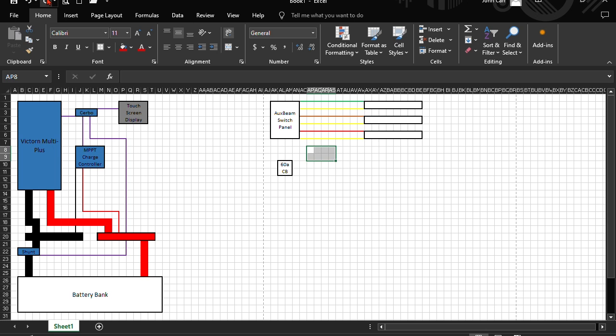Now, if we look, we've got a green and a yellow going to one load, a brown and a yellow going to a load, and a red and a yellow going to a load. You might say, but wait, most ground wires are black. That's correct, but you have to understand that now we're getting to a point where there might be a 120 volt wire running close to a 12 volt wire, and 120 volt wires that are black are the line wire or the positive wire. So using something like yellow is kind of a marine standard, and it avoids using a 120 volt line wire color in a ground situation on a 12 volt circuit.